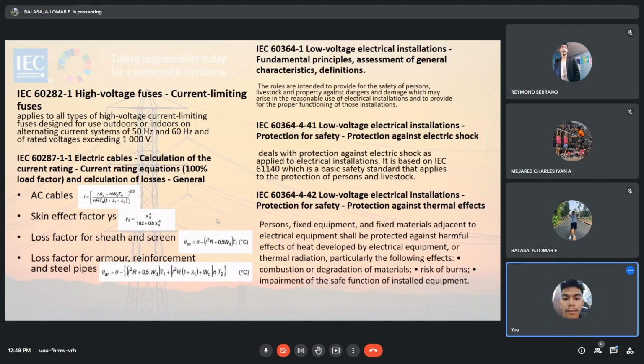This protection can be achieved by one of the following methods: preventing a current from passing through the body of any person or any livestock, or limiting the current which can pass through a body to a non-hazardous value. Fault protection, or protection against indirect contact, can be achieved by one of the following methods: preventing a current resulting from a fault from passing through the body of any person or any livestock, limiting the magnitude of a current resulting from a fault which can pass through a body to a non-hazardous value, or limiting the duration of a current resulting from a fault which can pass through a body to a non-hazardous time period.